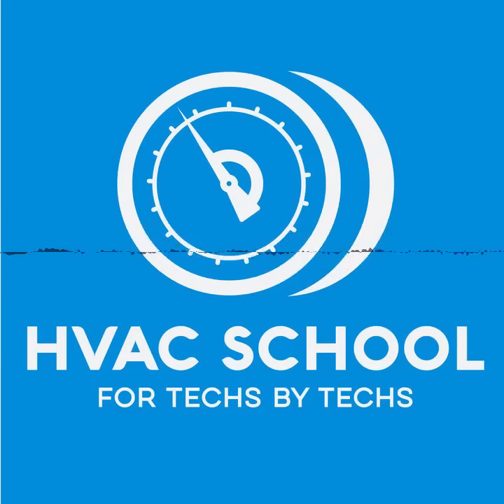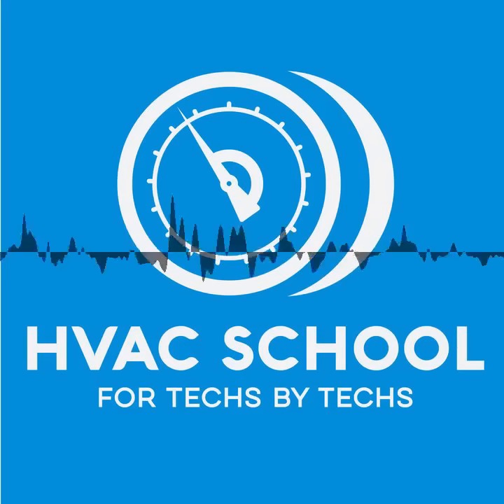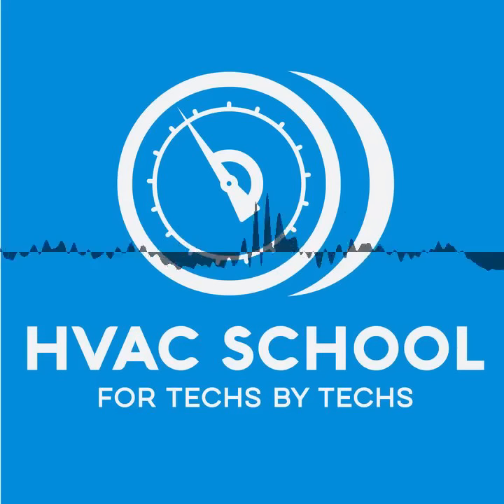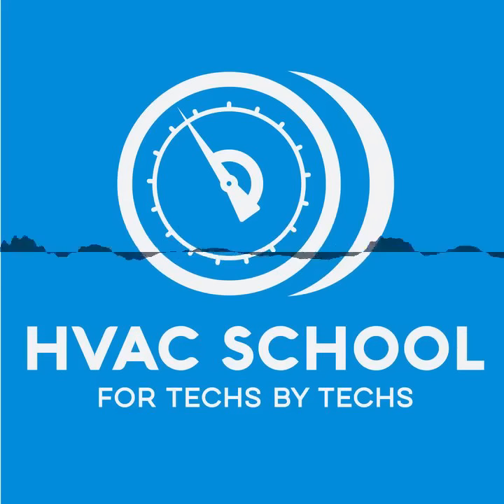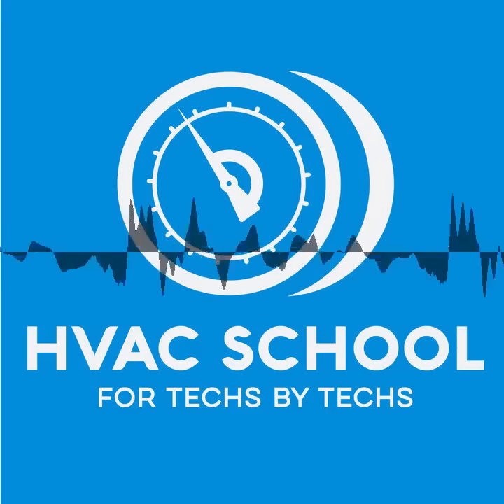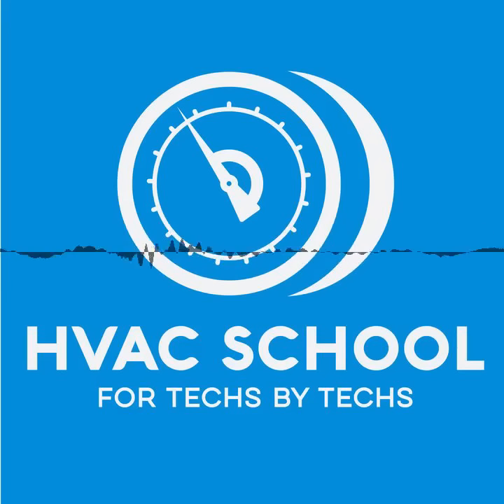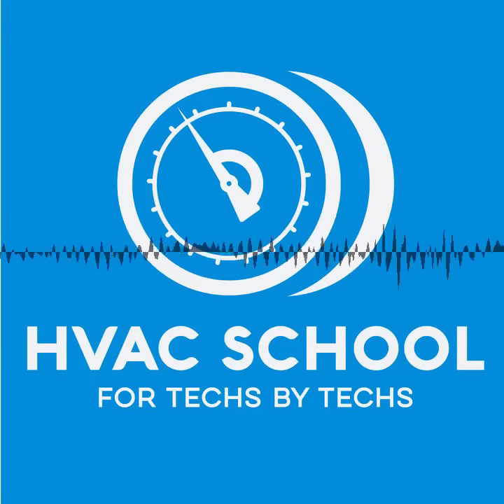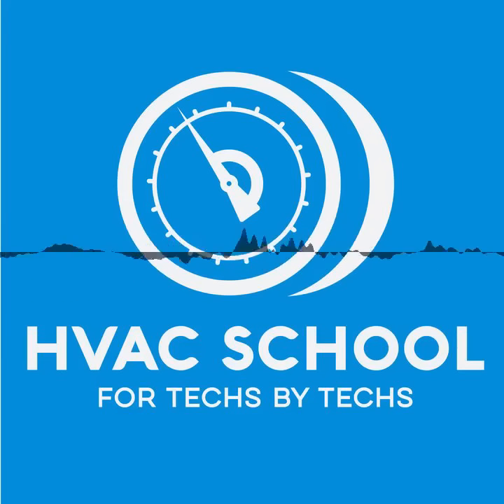Also, you'll see a lot of commercial applications where they use these with VAV boxes, and it works really well because you don't have to worry about flow. Your water is always being delivered at 44, so you can't possibly freeze up the unit. So you can run whatever fan speed you want. It doesn't matter. So they work really well with VAVs. I imagine it does still impact latent humidity removal slightly, though, depending on the amount of air volume. Changing the amount of air you're moving through the unit, you're changing the amount of air you're dehumidifying.